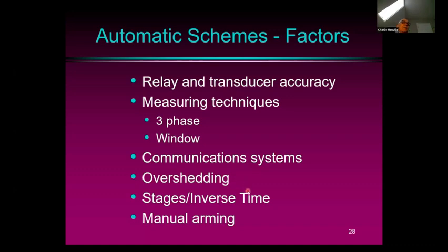Often you'll have load being shed in stages, either definite time or inverse time. So the lower the voltage, the faster the shedding. In many cases, you'll have manual arming of these load shedding schemes because of that danger, as I showed you before, where we had a load shedding scheme and it was armed and it started shedding load, but it was only undergoing test. So the controls that you use to make sure that the load shedding scheme doesn't operate unexpectedly are very important.